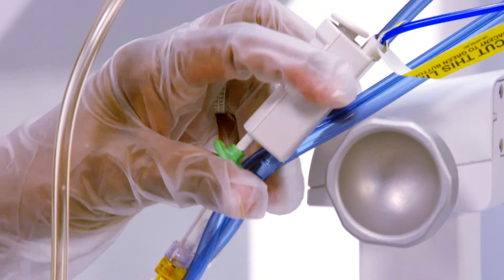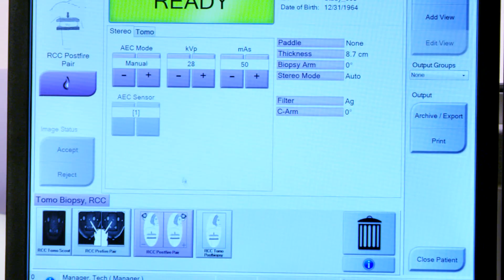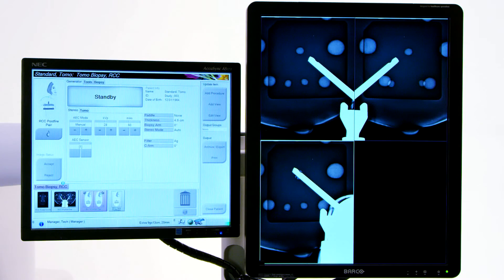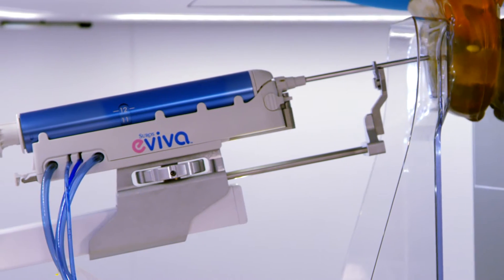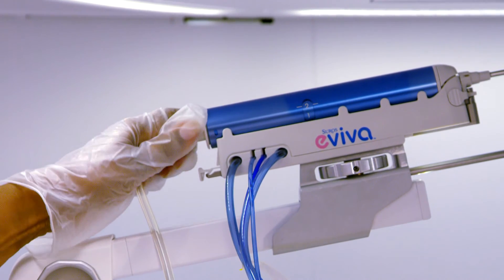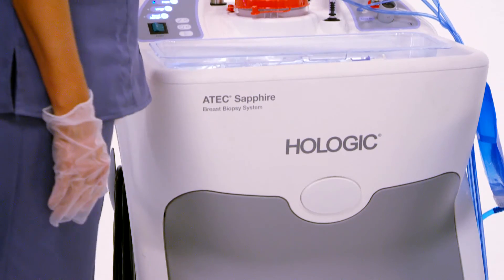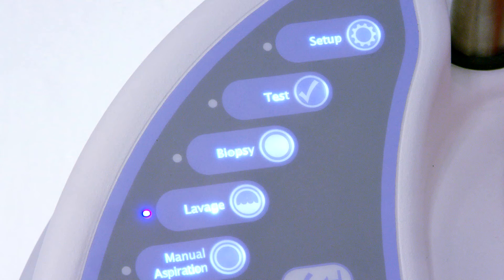The device is actuated via the remote firing button to advance the needle directly to the target site. If desired, we can take tomosynthesis or 2D biopsy pre- and post-fire views to confirm positioning. We're ready to collect the tissue specimen. Using Hologic's eViva system, the doctor is able to seamlessly deliver local anesthetic directly to the biopsy site during the procedure without any interruption. The console is then placed into lavage mode to irrigate the biopsy area with saline while the tissue samples are being verified.